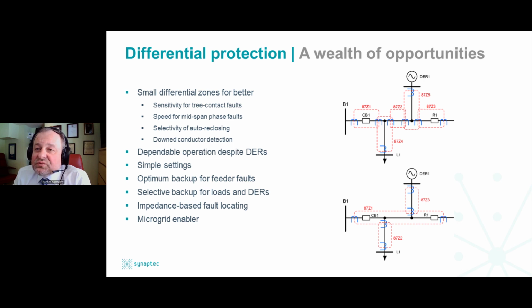I would have a better way to provide backup. So even if I use time over current as a backup, I have CTs now located closer to the fault, so my coordination times are not going to stack up that high and I could trip faster. I have CTs in front of my loads and DERs, so I could provide better backup for faults within loads and DERs. Now I have voltages from both ends of a faulted section, so I am able to run impedance-based fault locating. And because I have visibility inside that feeder, I could monitor or even protect a microgrid. So again, nothing new. We know that this stuff is very powerful and it solves a whole range of problems, not only wildfires.